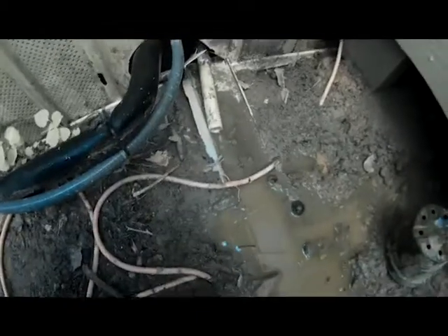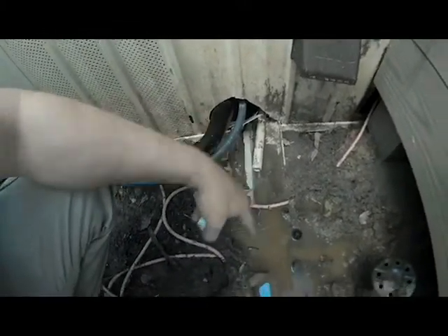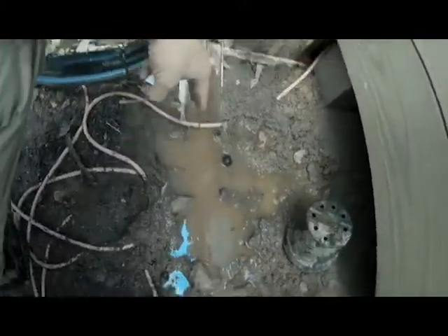Alright, I basically went up under the house. I don't have any sags in my drain line, but what I did find is right here where the drain leaves the house, there's a lot of water standing. And what will happen is if you get a whole lot of water, there's nowhere for this water to go. If it starts running back in the drain, it'll actually cause a clog in the drain and cause the drain not to drain properly. So what we've got to do is let the customer know that something's got to be done with this water, so basically to keep that drain from stopping up.